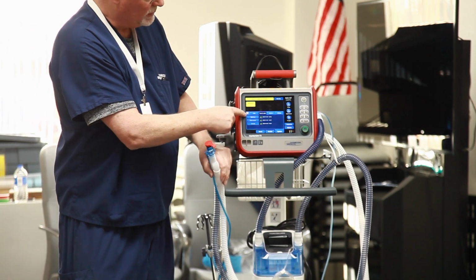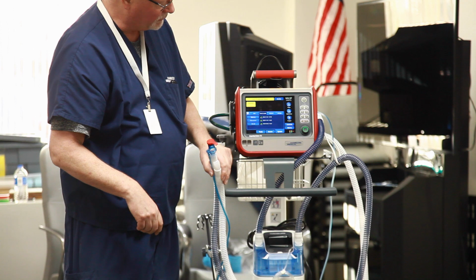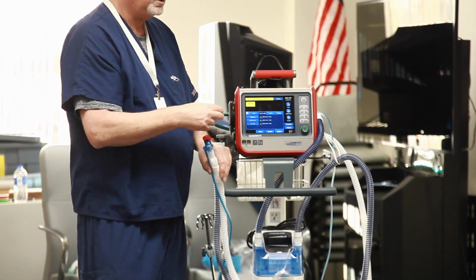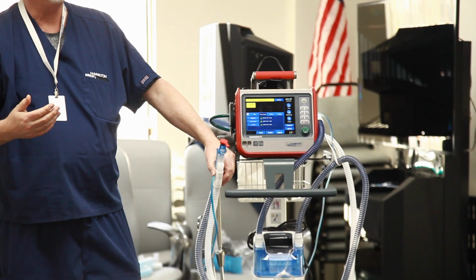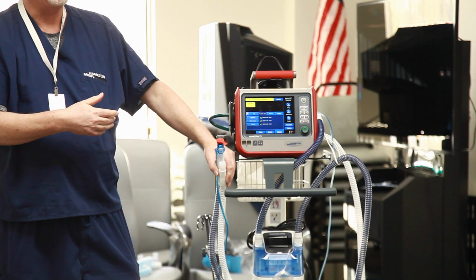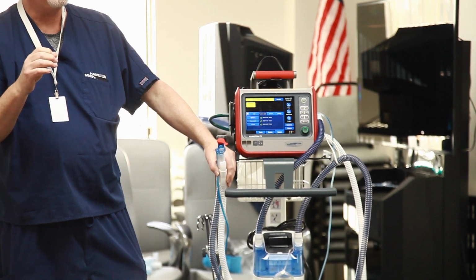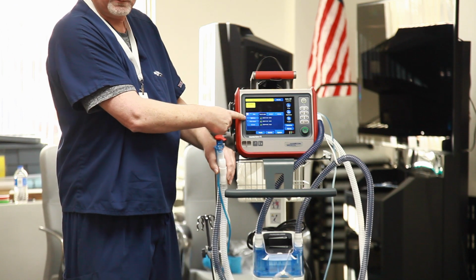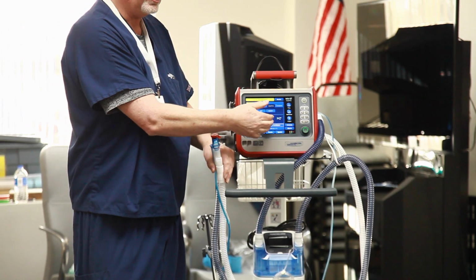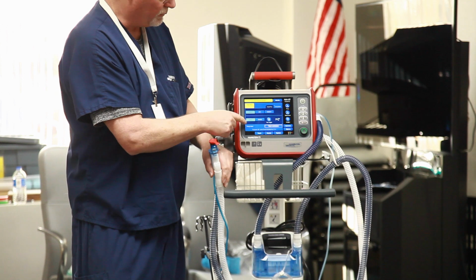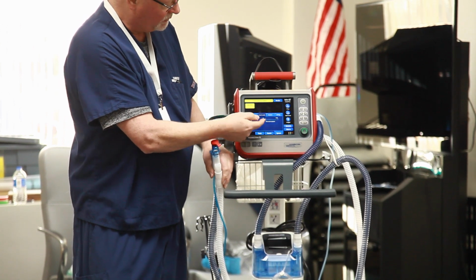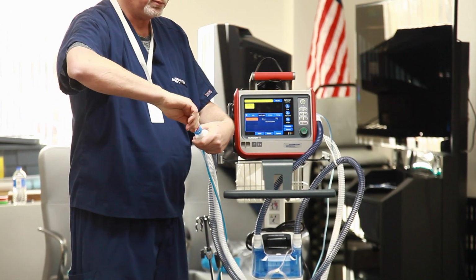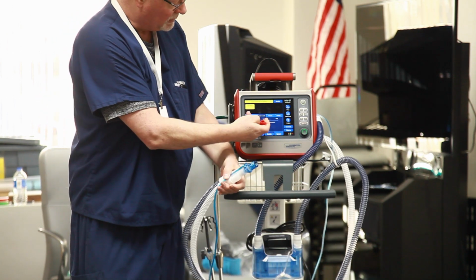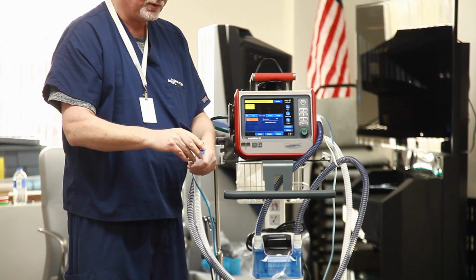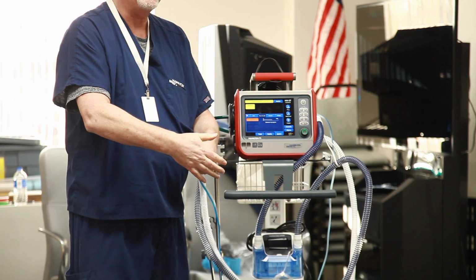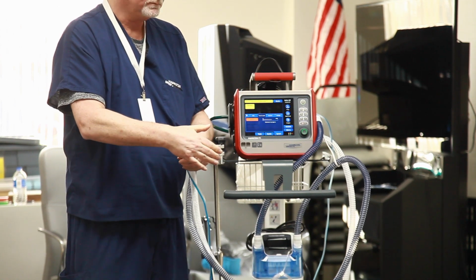So the two things you do need to do are a tightness and flow sensor check. Tightness, I think you heard me say that. We ended up with some older software in here, not the newest software we have. The newest software might say leak test or something like that. It won't say tightness. It'll also have pictures on it to walk you through that. So tightness: disconnect patient, unplug the end. It's going to tell you to block the end or tighten the system. Either put this over it or put a gloved hand over it and keep it on here.